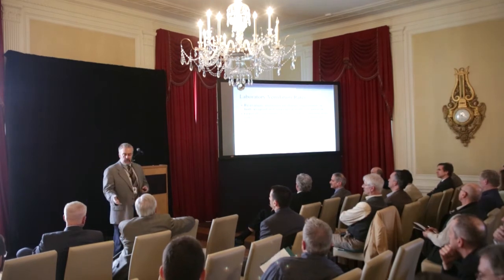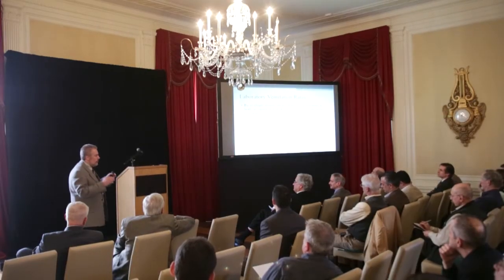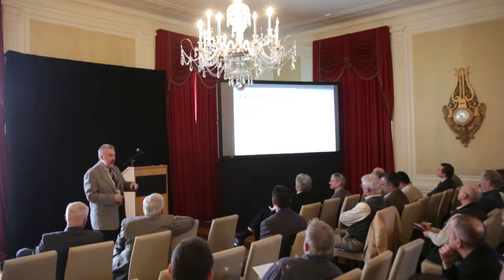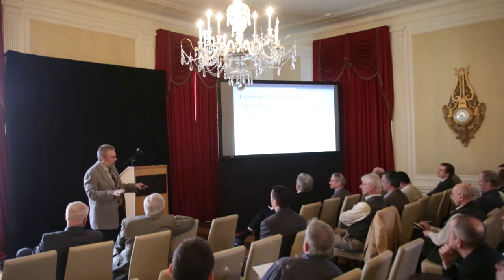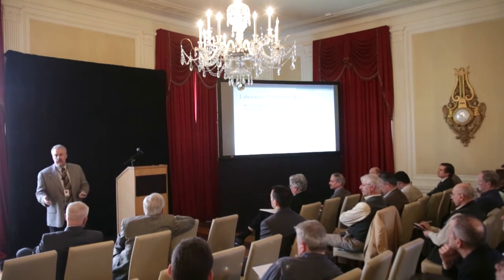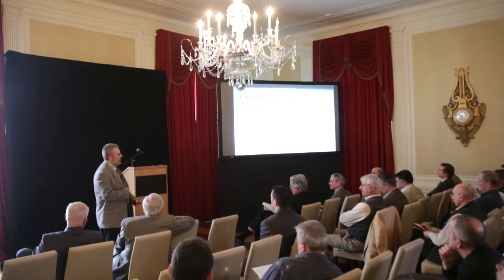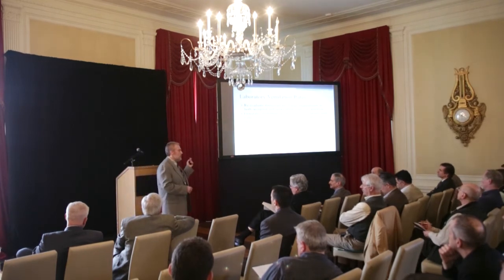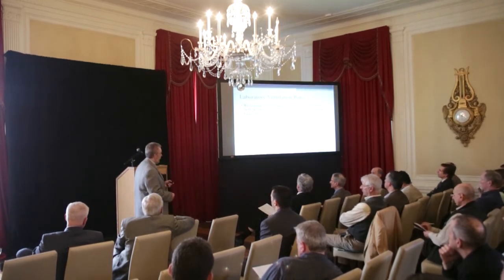And again, that can be the dilution rate like you're talking about. There maybe isn't a very good correlation between air changes and dilution. You can make a whole bunch of arguments. Again, somebody said it earlier, I could spend hours talking about that and it would still be going back and forth. We found generally they were in 7.5 to 9 air changes per hour. It's 100% outside air unit. Like I said, $5 or $6 per CFM, huge savings. Absolute huge savings. Had a DDC system in it, went in and changed set points. Looked at the balance of the distribution, tried to maintain the pressure relationships. You guys all know that we're running these labs under negative pressure, and we were done. Walked away with a minimum amount of money into this and a huge amount of savings.